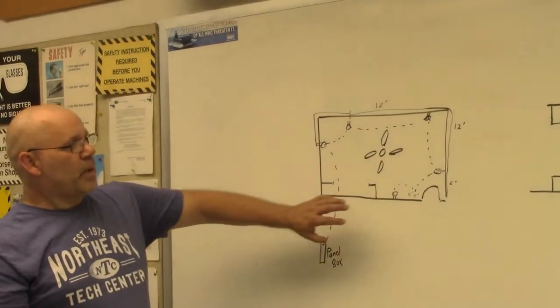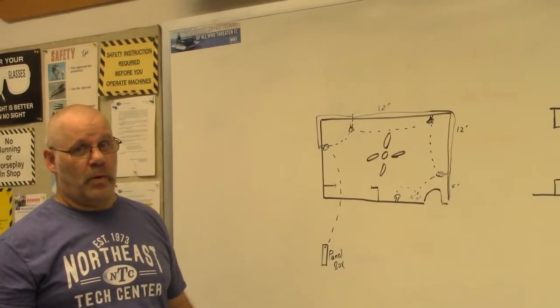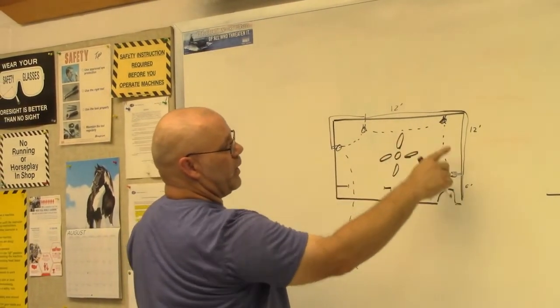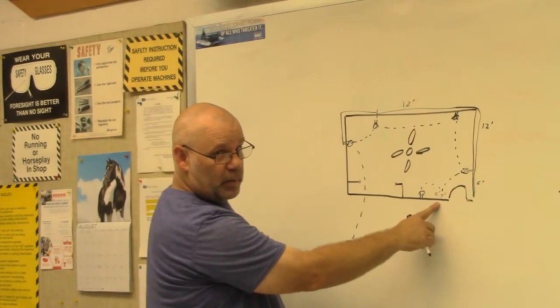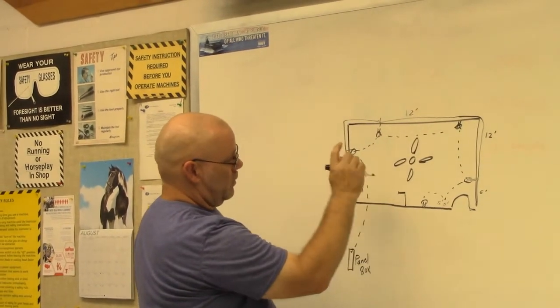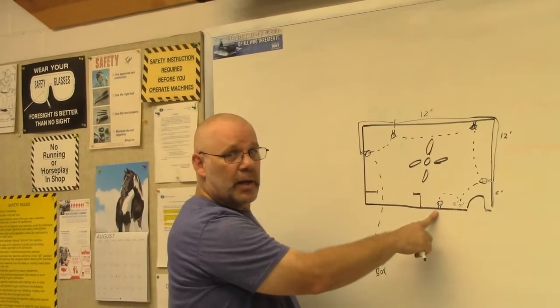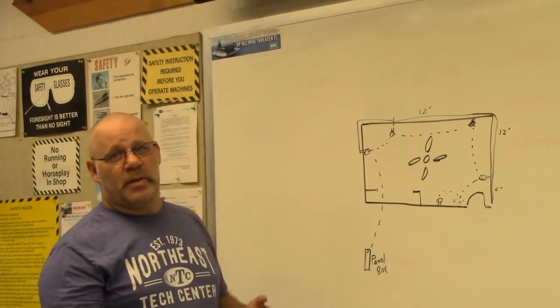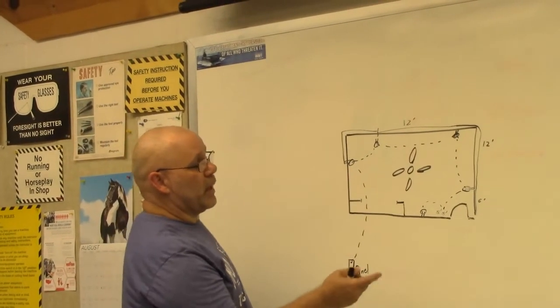Now, how many of these things can I put on here? Well, code says I can put up to 12. So if you count what we have, we've got one, two, three, four. You have to count this two, one for the light kit, one for the fan. So one, two, three, four, five, six, seven items on this, which would be a good circuit, because most of the time you want to have somewhere between six and nine. You really don't want to get 12 on there, but you can get up to 12.